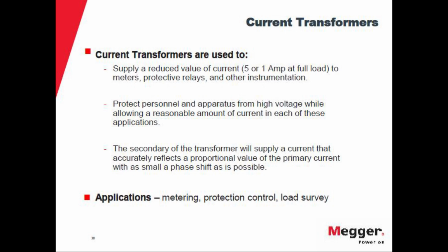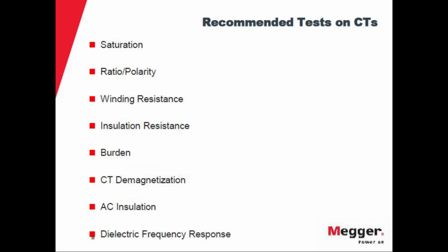And in addition to providing information to the instrumentation or the control apparatus, current transformers are also used to protect the personnel from the high voltage environment. And you can see them for special applications in metering and protection. Mainly these are the two main CTs that you can find out there in the substation world. The tests that you perform on the CT are basically saturation, ratio and polarity, winding resistance, insulation resistance. You perform demagnetization, and as separate tests, you can do AC insulation and dielectric frequency response.